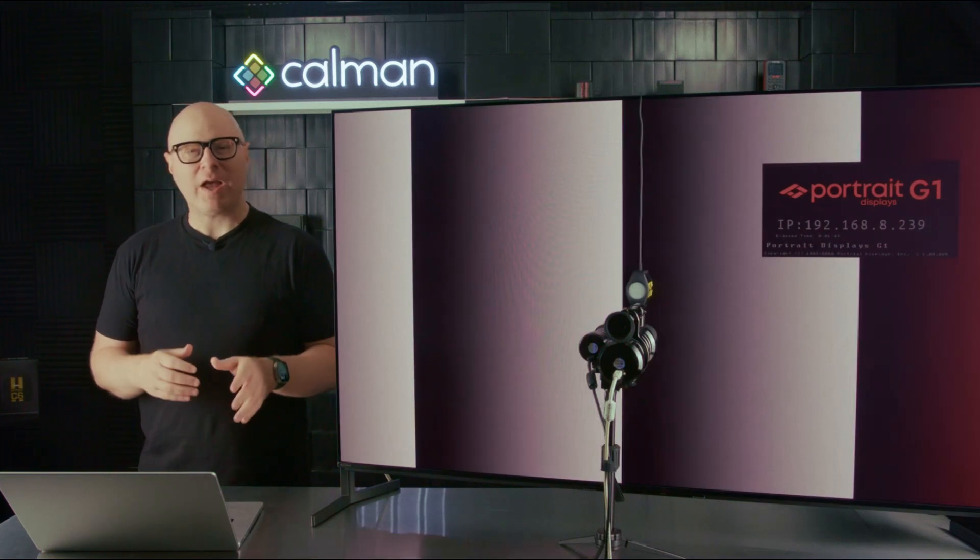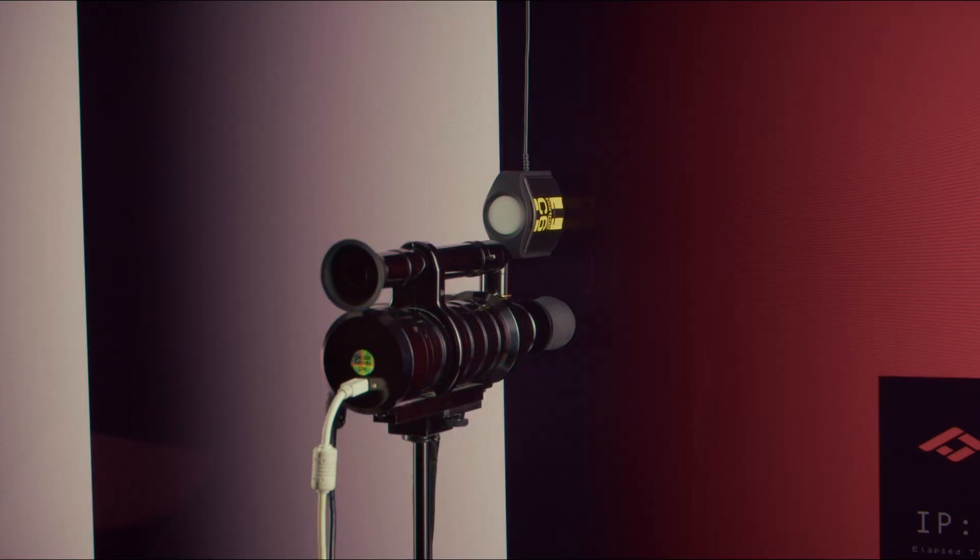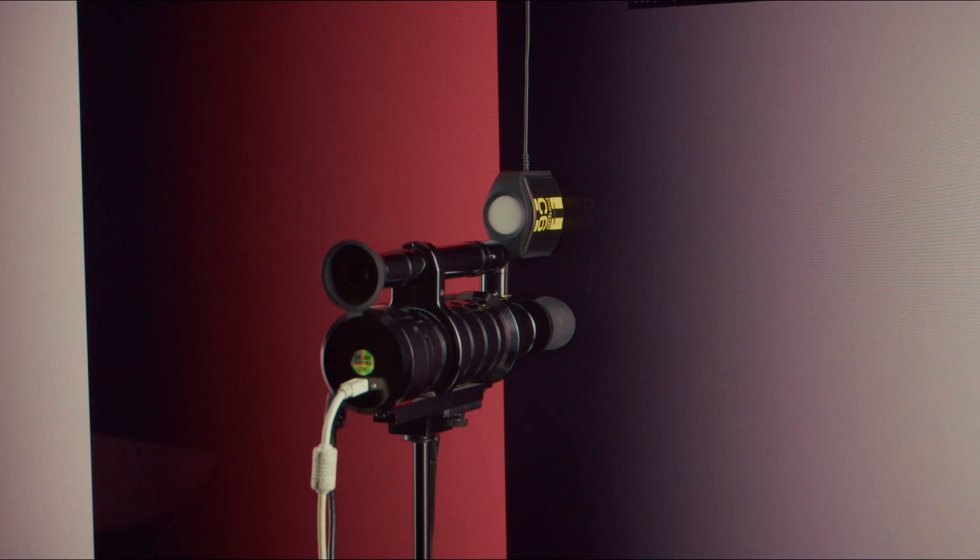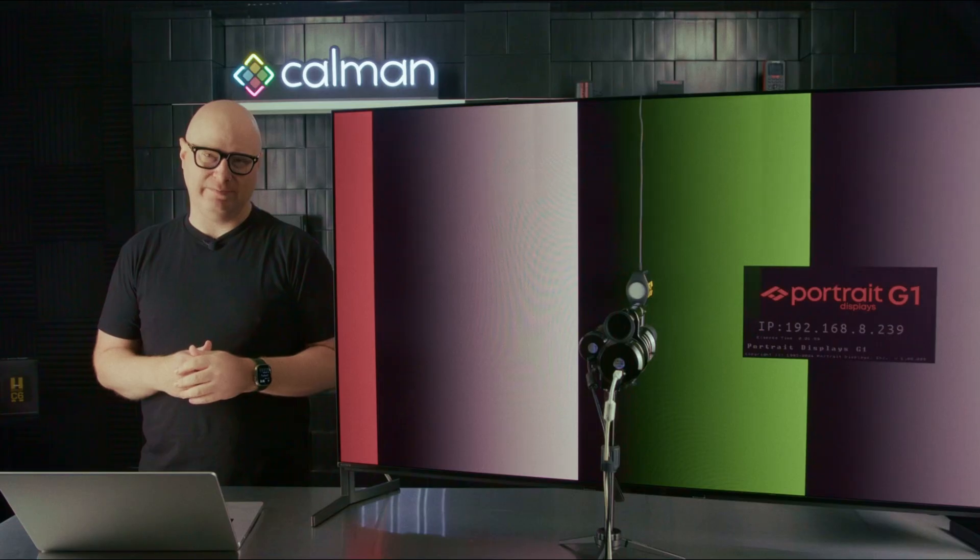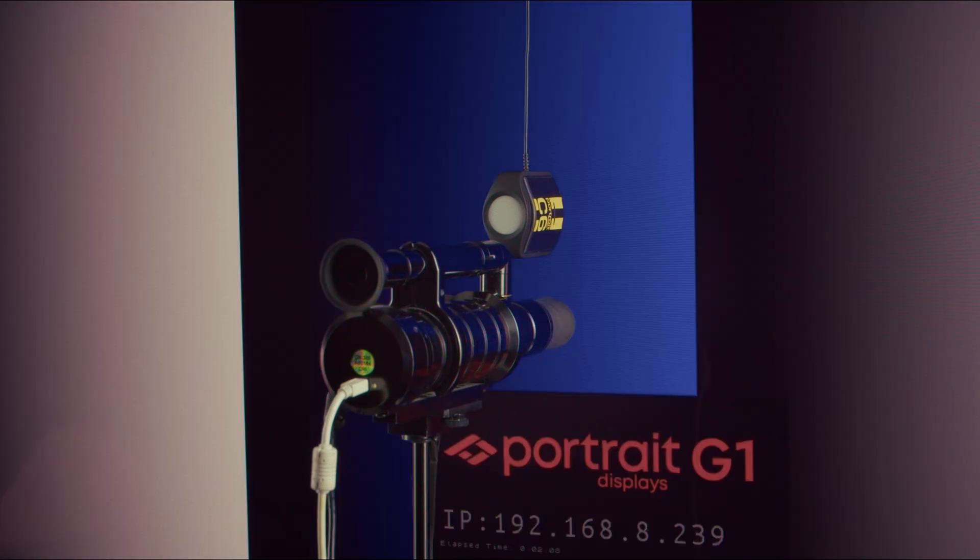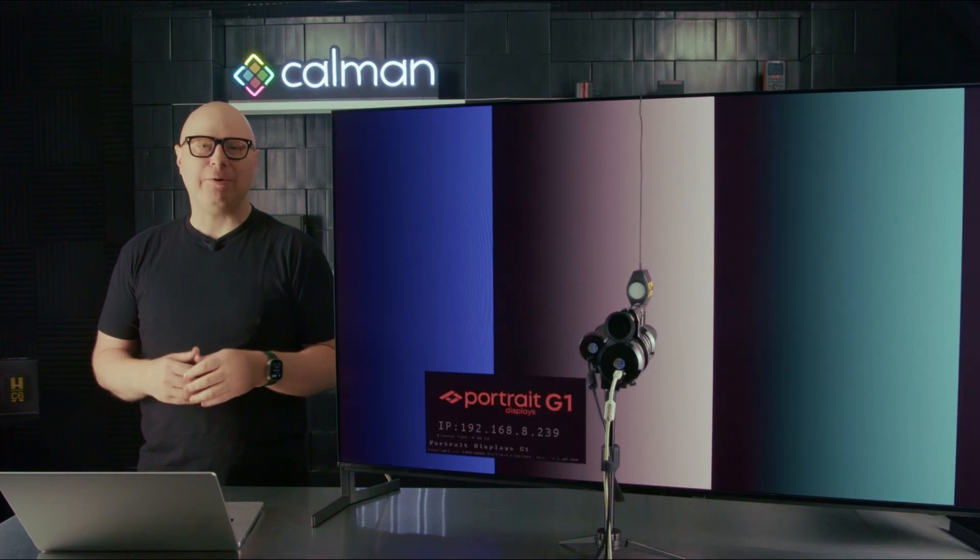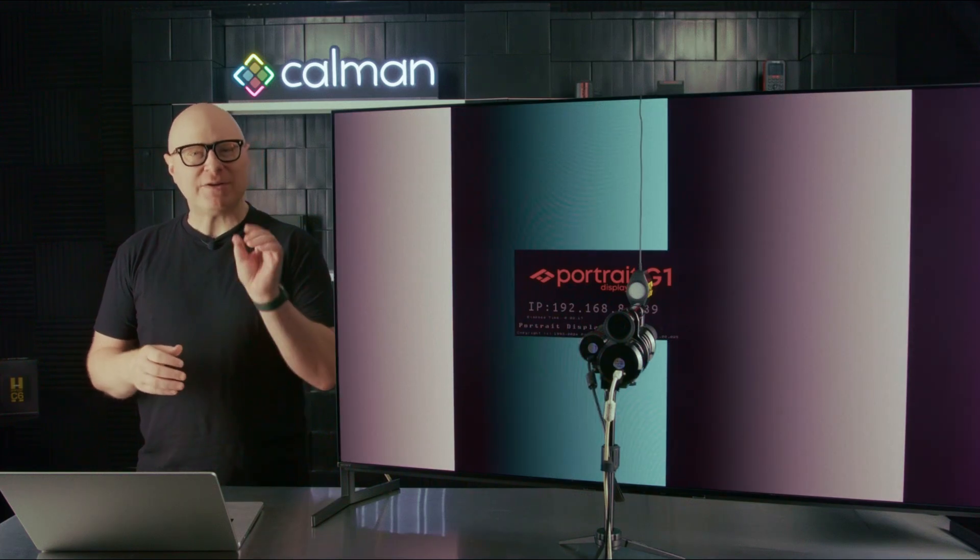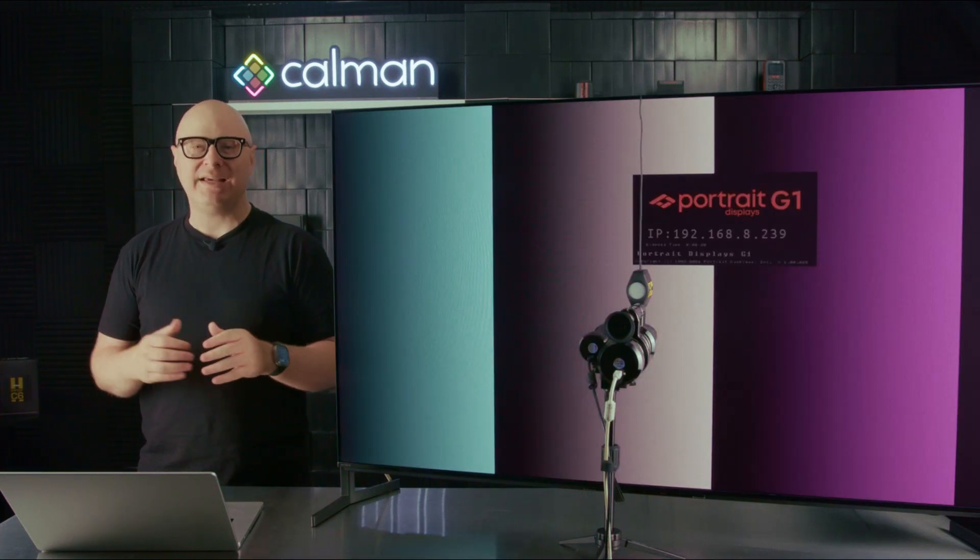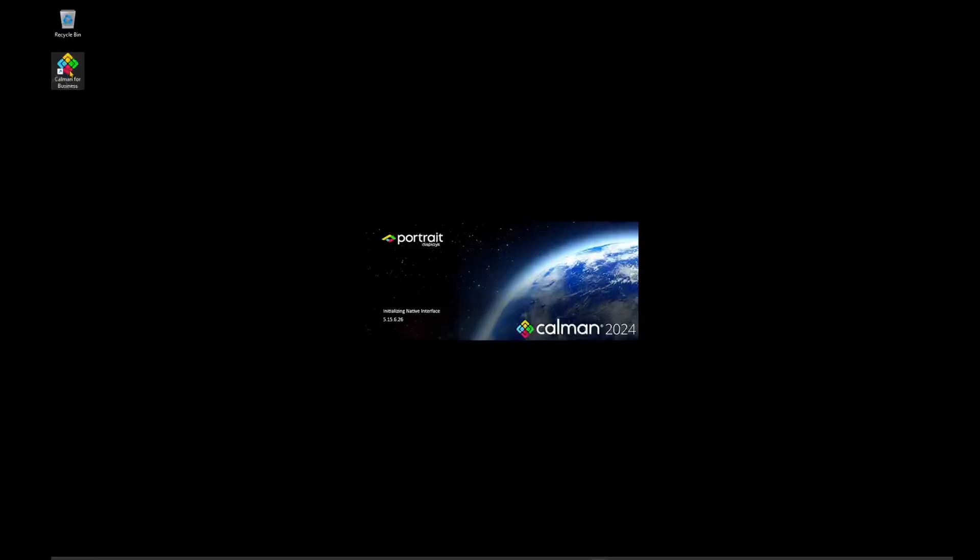Today, I'm using our Portrait Displays C6 HDR5000 Colorimeter and the Colorimetry Research CR300 Spectroradiometer. We have both of these set up on the Sony A95L QD OLED. The C6 HDR5000 is centered on the display and the CR300 is set up slightly off-center. In a perfect world, the C6 and the CR300 would measure exactly the same spot, as measuring two different locations may not take into account slight changes in panel uniformity.